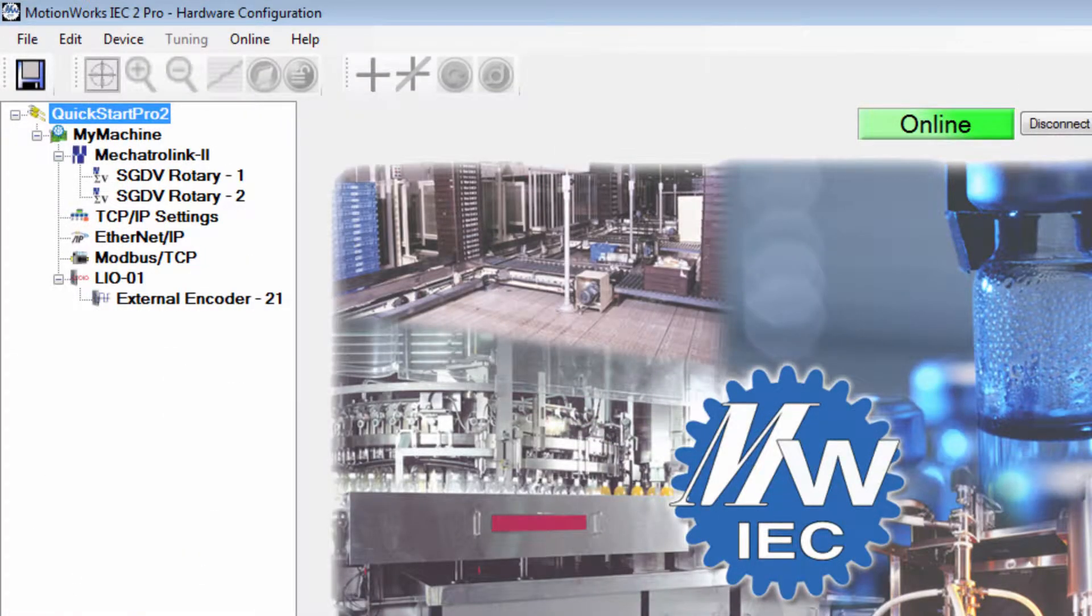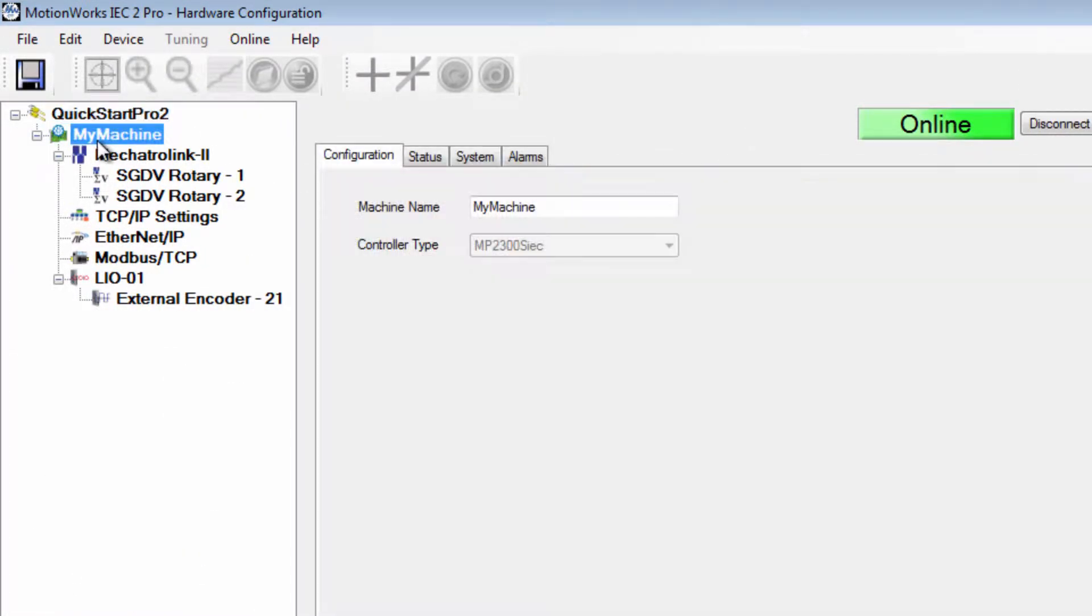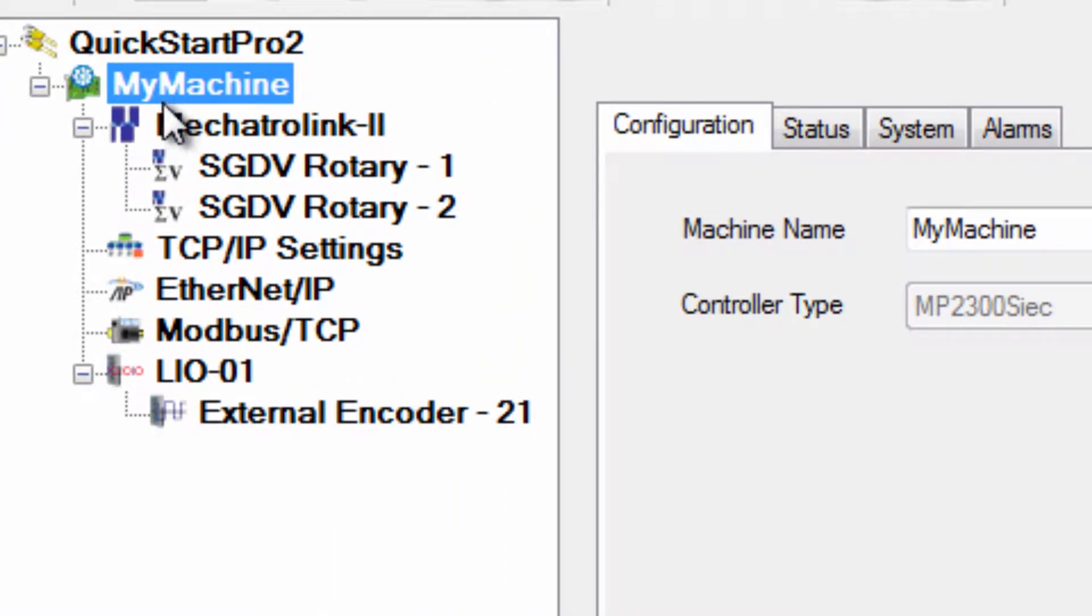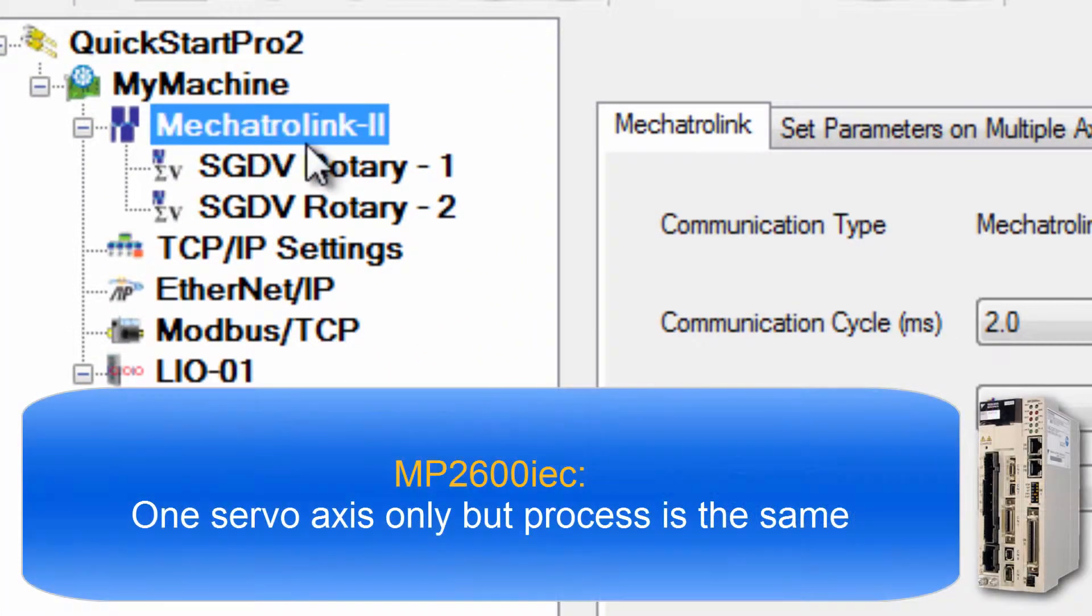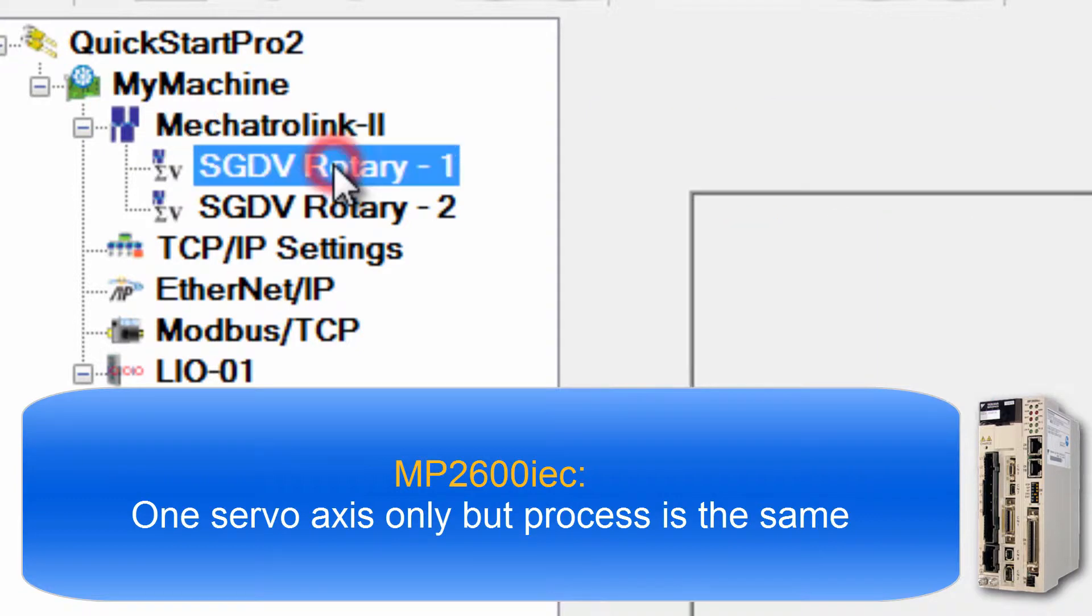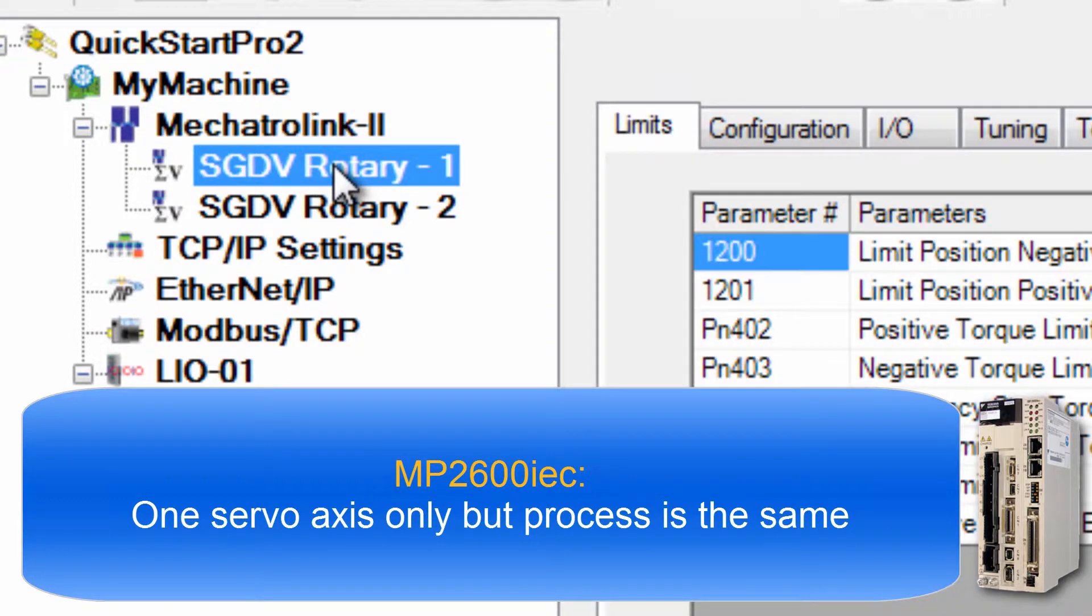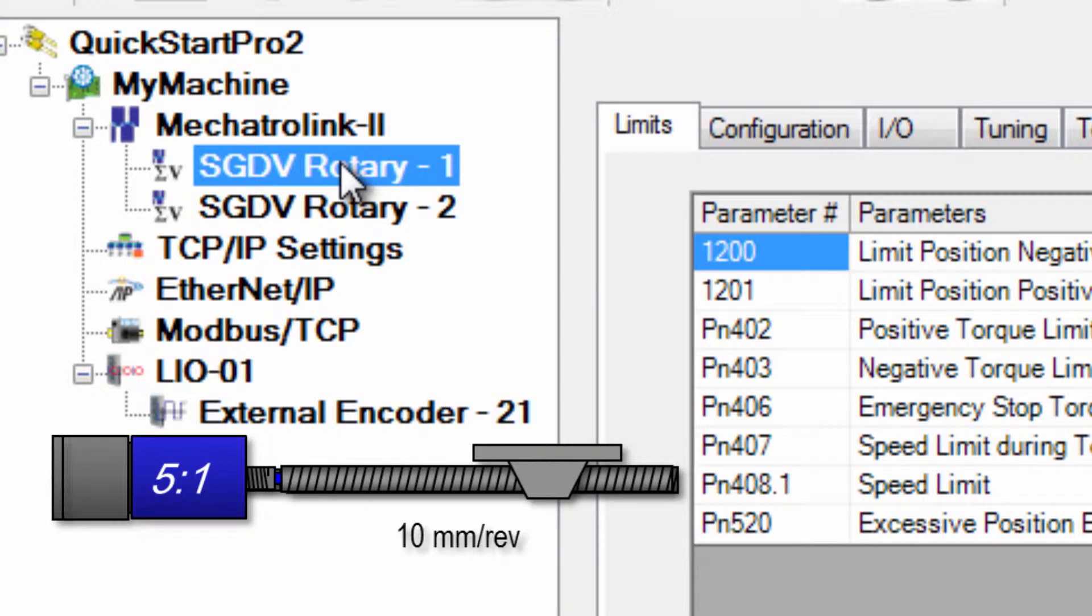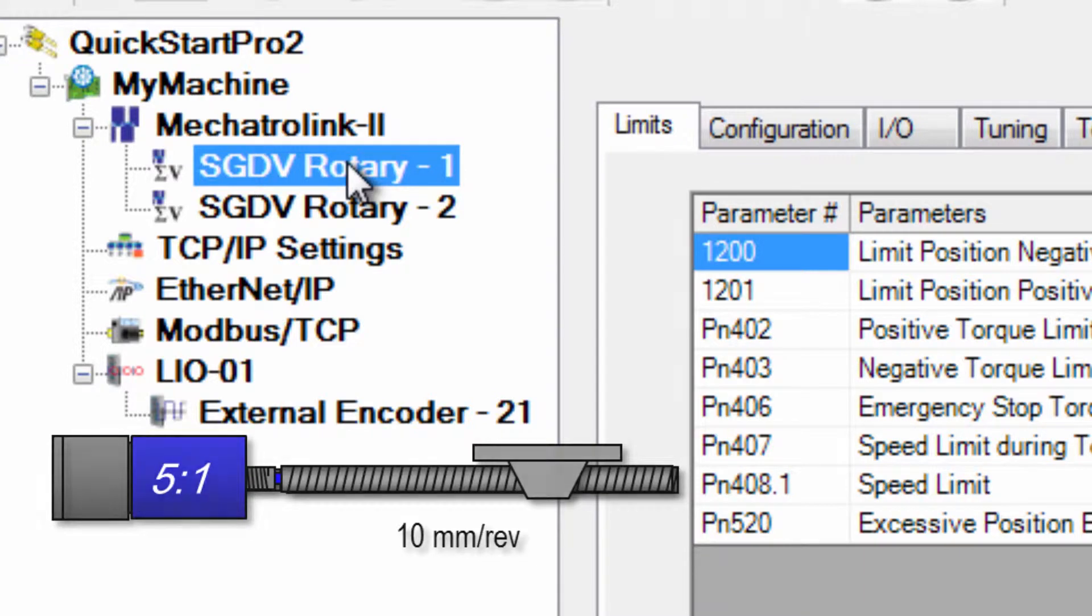Now I'll go through a different example in detail. I have an MP2300 SIEC controller with two different Mechatrolink servo axes. Sigma 5 SGDV Rotary Axis 1 is connected to a 10 millimeter ball screw actuator through a 5 to 1 gearbox and I would like to program this axis in units of millimeters.